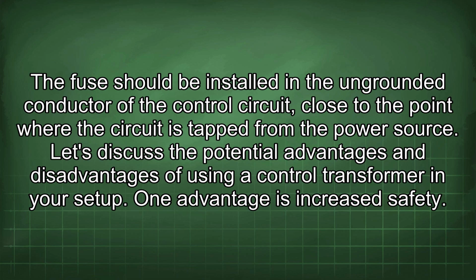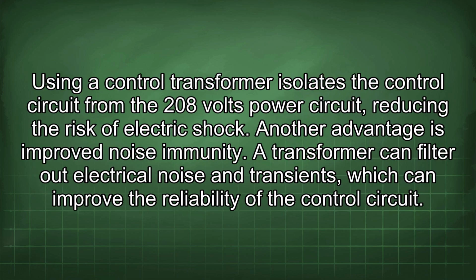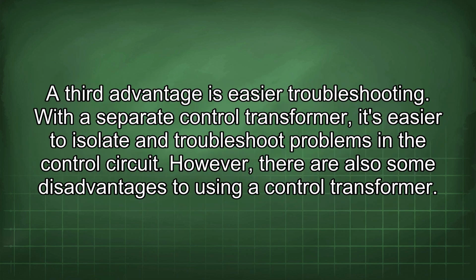Let's discuss the potential advantages and disadvantages of using a control transformer in your setup. One advantage is increased safety. Using a control transformer isolates the control circuit from the 208 volts power circuit, reducing the risk of electric shock. Another advantage is improved noise immunity. A transformer can filter out electrical noise and transients, which can improve the reliability of the control circuit. A third advantage is easier troubleshooting. With a separate control transformer, it's easier to isolate and troubleshoot problems in the control circuit.